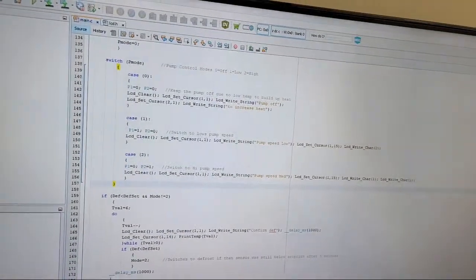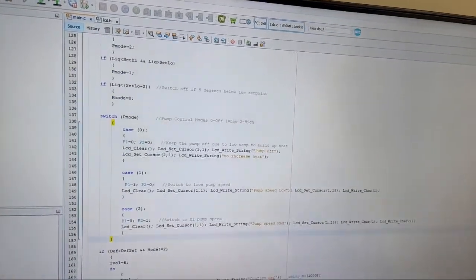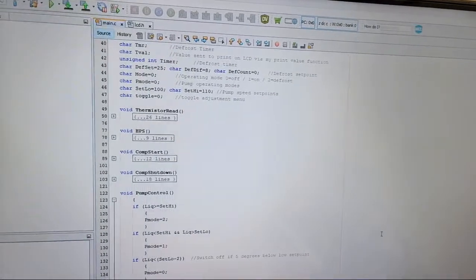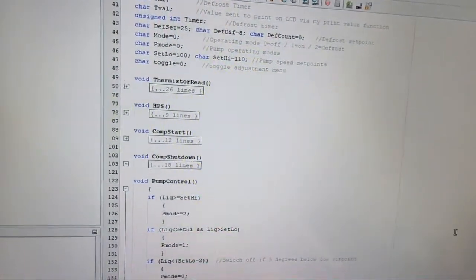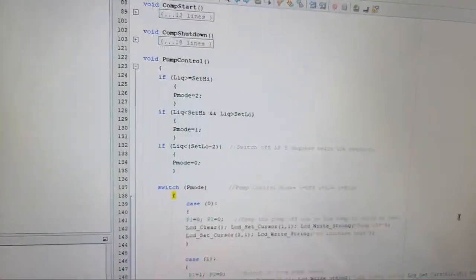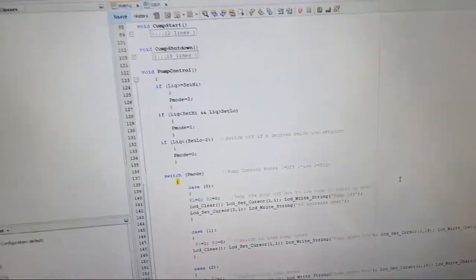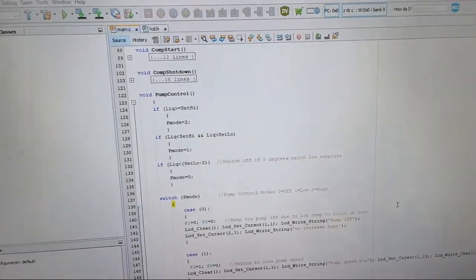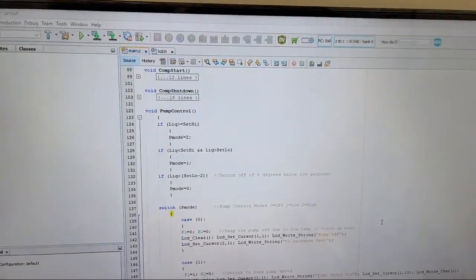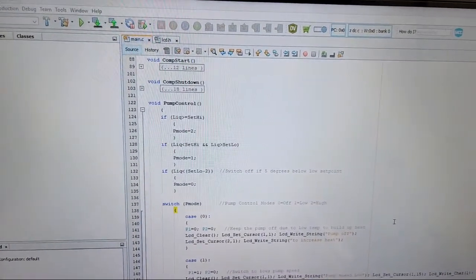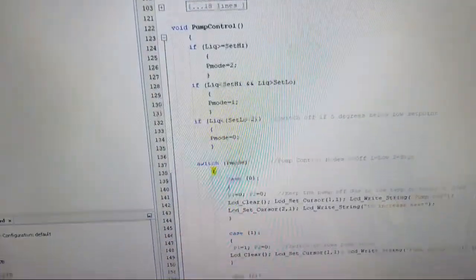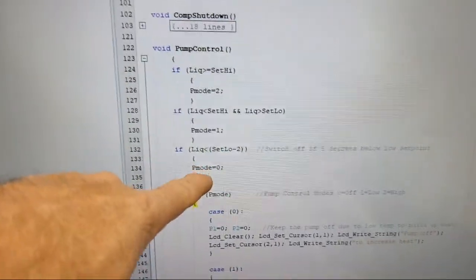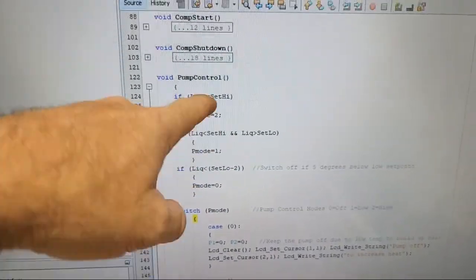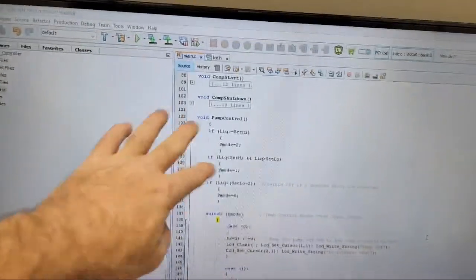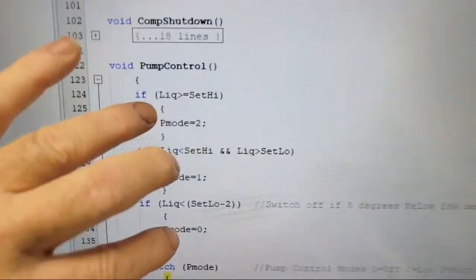So I just have some of this C code. I've been tinkering on it. I have all these different functions. So pump control. Basically, I have my operating modes. I have my main operating mode, which is 0 is off, 1 is when it's heating, and 2 is defrost. I also have pump control modes, with 0 being no pump, 1 is low, and 2 is high. And these just set the thresholds based on liquid line temperature.